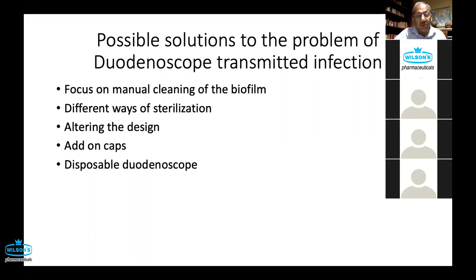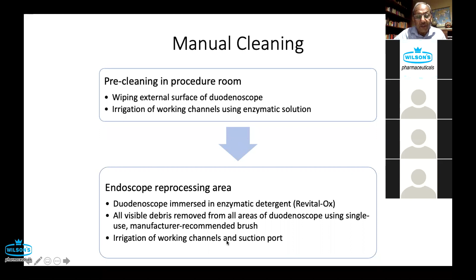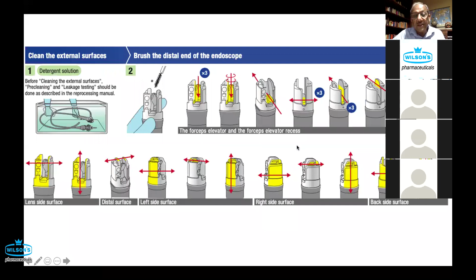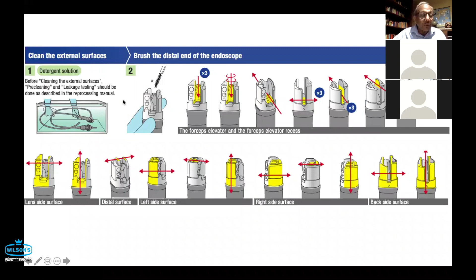In manual cleaning, we all understand, we talked about this cycle right in the beginning, that the duodenoscope is immersed in the enzymatic detergent. Before that, there is wiping of the external surface of the duodenoscope and irrigation of the working channels using enzymatic solution, and irrigation of the working channels and suction port after immersing in the disinfectant. Now, these are the charts that I have taken from the Olympus company, and this tells you how much time each person has to devote. The technicians have to be fully trained and supervised.